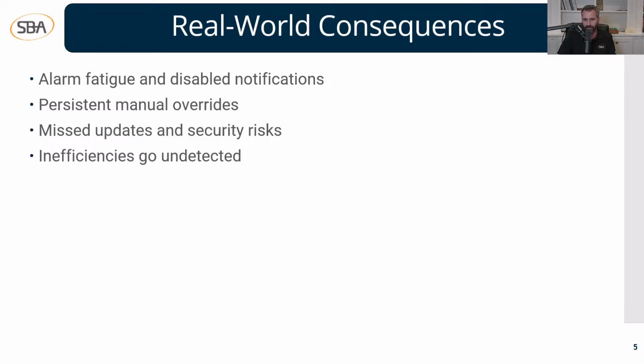Another issue is controllers left in override - we touched on that already, persistent manual overrides, and that can cost energy. Think about if we left a fan on continuously forever because we overrode it and it just keeps staying on. Or the chiller never shuts off - when the building becomes unoccupied or the outside air goes below a certain set point, say 50 degrees, and the chiller's still running even though we're bringing in outside air and economizing with our air handlers. Maybe that chiller was in override - that's going to cost a lot of money when it doesn't have to.